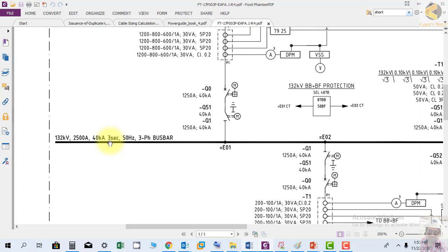The concept here is: if you want to increase the fault duration by one second, you need to approximately double the conductor size.